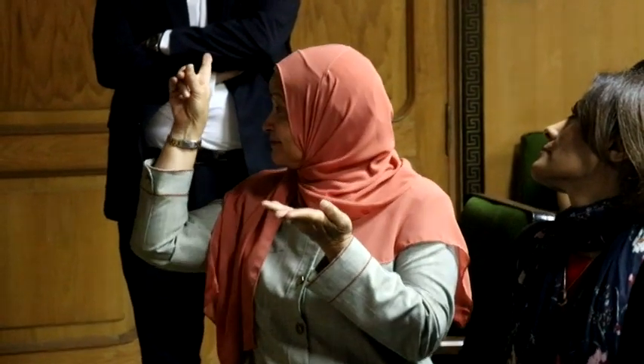The engineers and technicians of Abbott, yeah. The cable has an atrial port and a ventricular port, and they make us measure everything with one port, like the ventricular port. Is that okay? I would put it in the right port. If I was measuring the atrium, I'll measure the atrium. If I'm measuring the ventricle, I'll measure the ventricle. Sure, we'll make that change. So it makes a difference? It can make a difference, yeah, particularly with the sensitivity. It is using slightly different band passes on the atrial leads. It usually doesn't make a lot of difference, to be fair. You often don't see much difference, but there is a small potential.